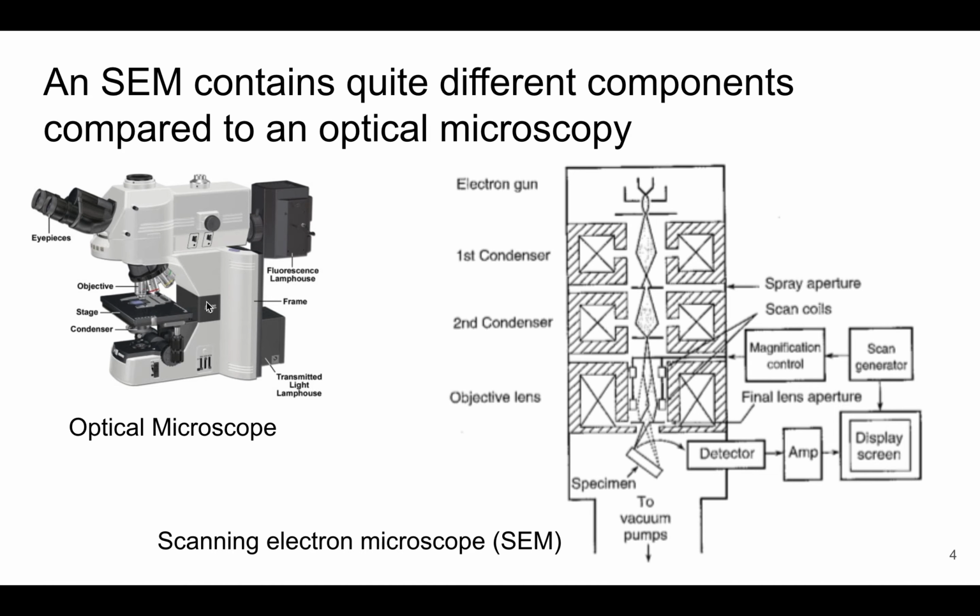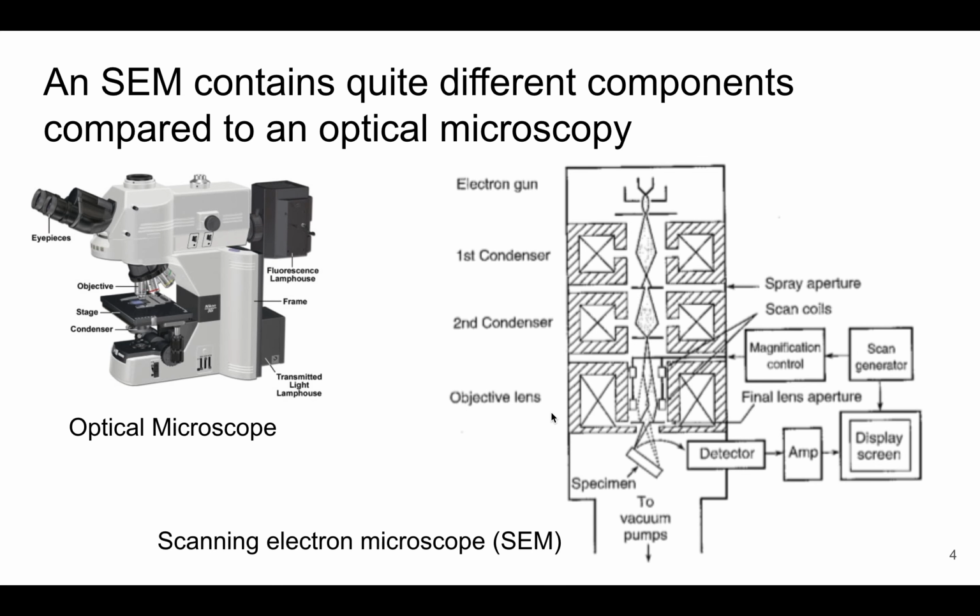Whereas a light microscope looks at the whole image at once, so the whole spot size is illuminated at once, in SEM the beam is rastered, moved, scanned across the surface to give a much larger image than the single beam. So we need these scan coils. This is the defining feature of the scanning electron microscope, and the part that you'll never find on the light microscope over here.